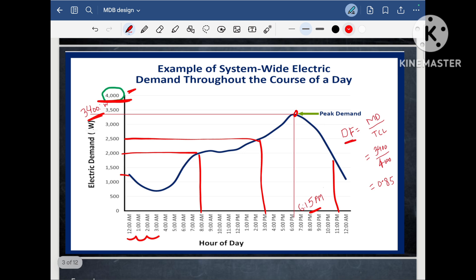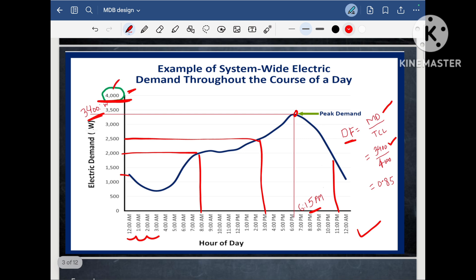So what is demand factor as per the definition? It is the ratio of maximum demand to the total connected load. So the maximum demand for my home for this day is 3400 Watt and the total connected load is 4000 Watt. When I divide this, it comes to 0.85. So I can say that for my home, which has a total connected load of 4000 Watt, the demand factor is 0.85 and the maximum demand for this day is 3400 Watt.